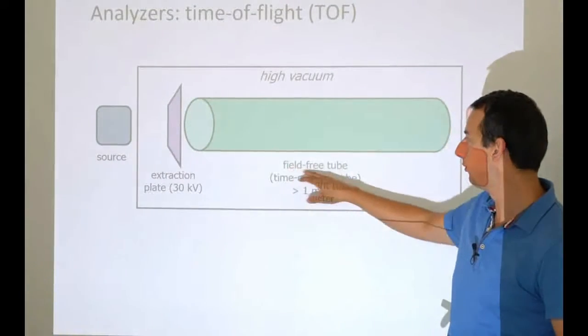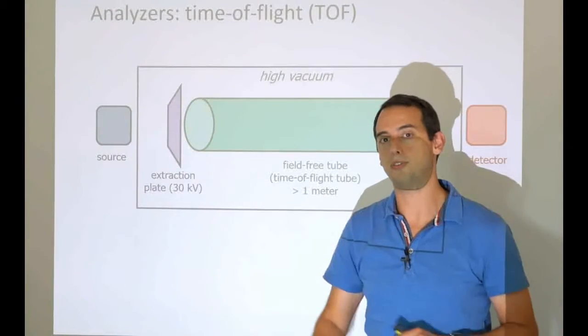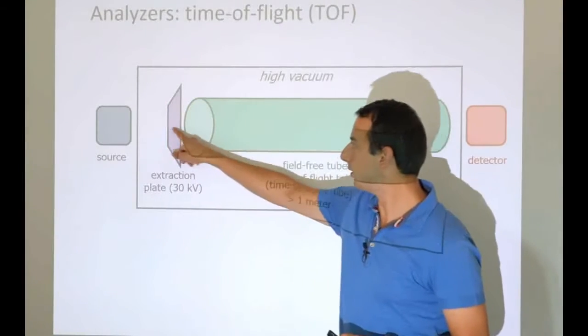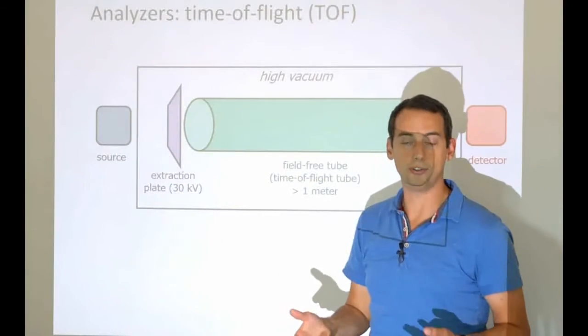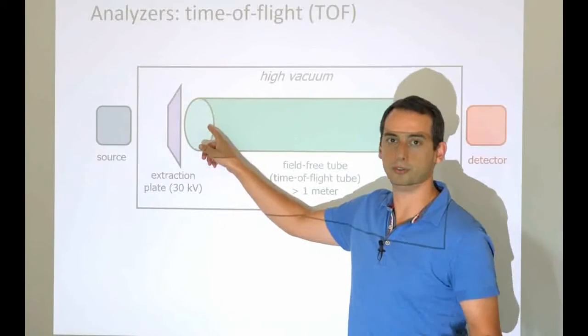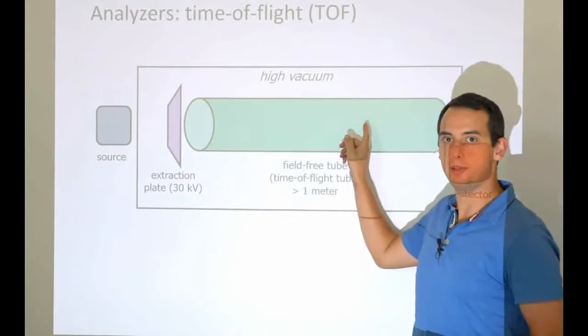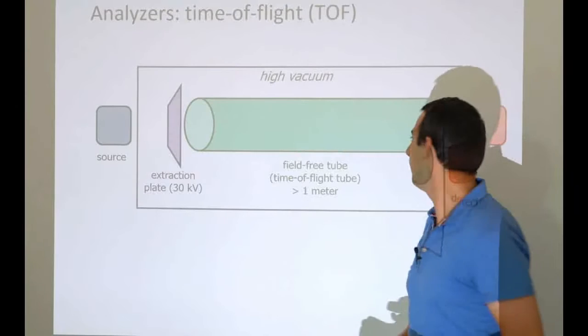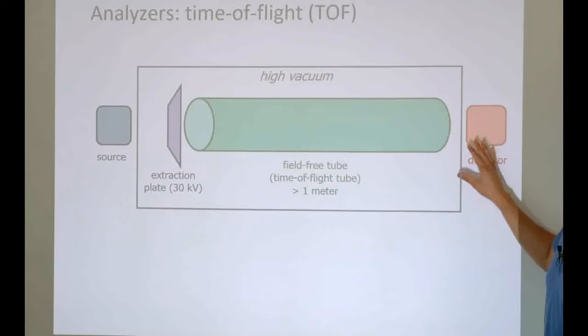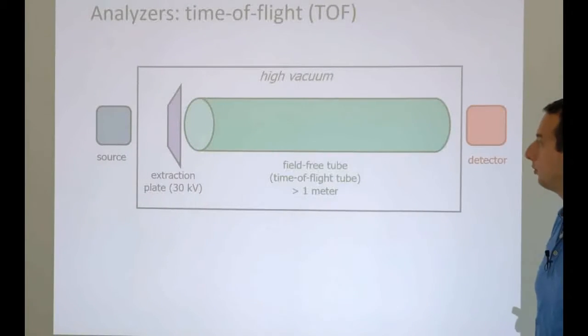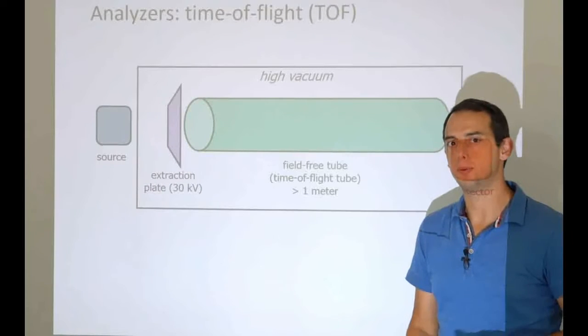That's why they call this a field-free tube — it's essentially just a vacuum tube machined to very precise dimensions. The ions that have been accelerated through the electrical field generated by the extraction plate will have a certain velocity. With that velocity, because there is no resistance from the air (it's vacuum) and because there is no electrical field, they will just continue with this speed and travel along the length of this tube. At the very end we will have a detector, which will be able to find out when a molecule has traversed this field-free tube. These tubes are typically longer than a meter, and there's a reason why they're long — but we'll get back to that.